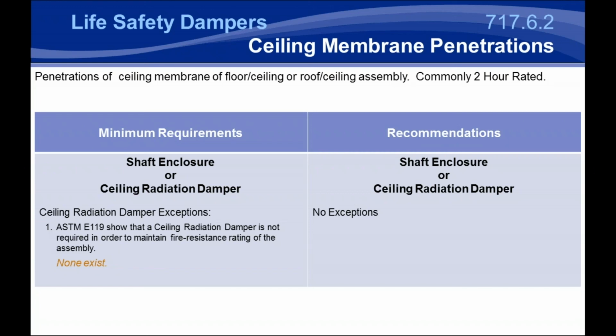Now, what you can do, if there is no ceiling radiation damper allowed, is use a shaft enclosure for this type of assembly. And typically we recommend that when you're going through a rated ceiling or floor ceiling, even though it's only going through one story, but that floor ceiling can't have a horizontal fire or fire smoke damper, at that point you need to use a shaft enclosure. And that's your way to get past that requirement.